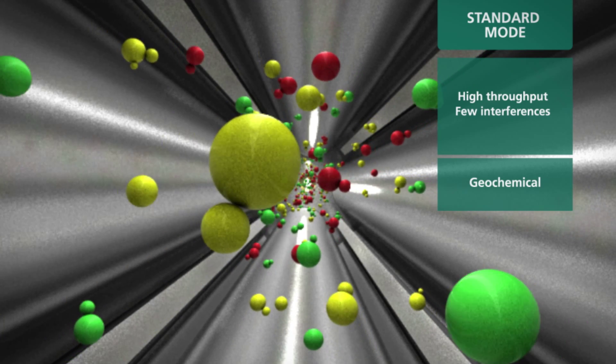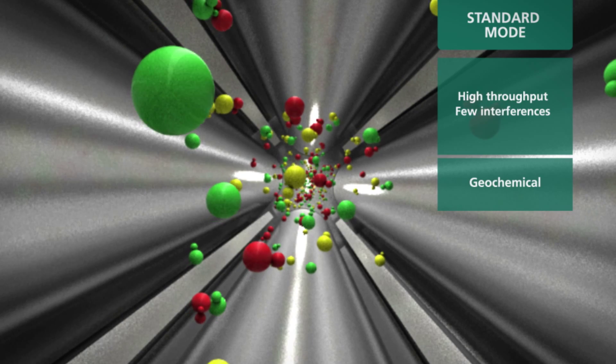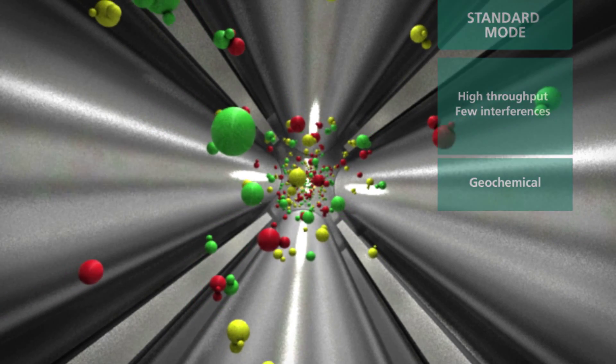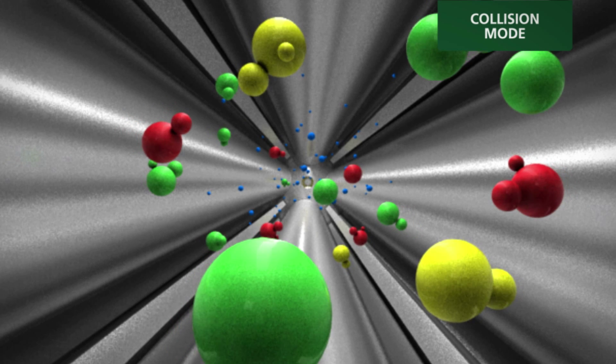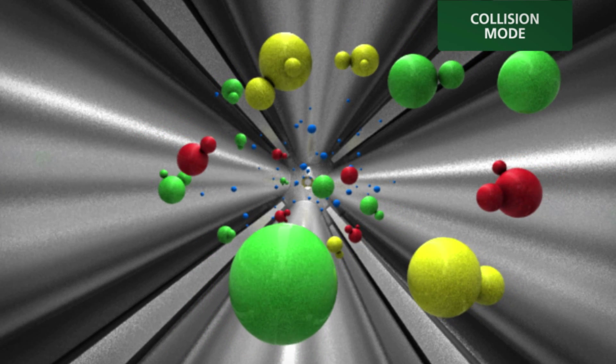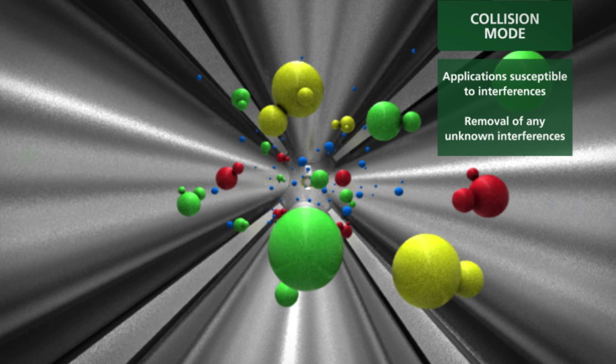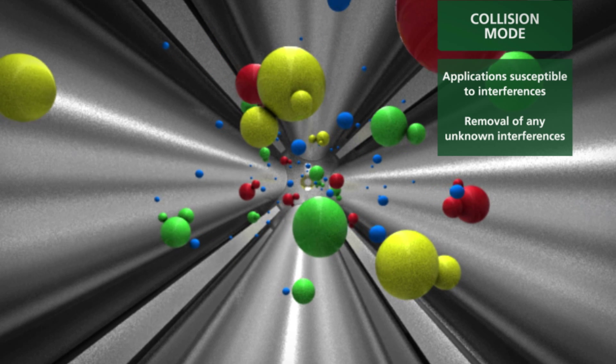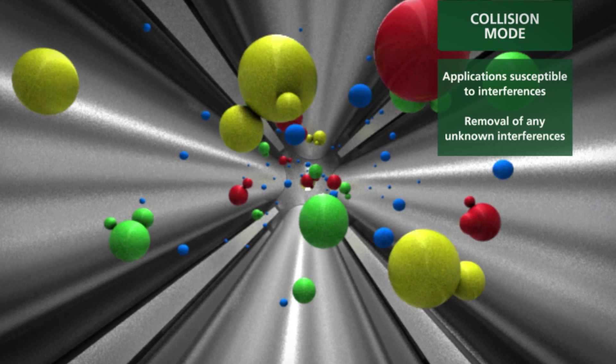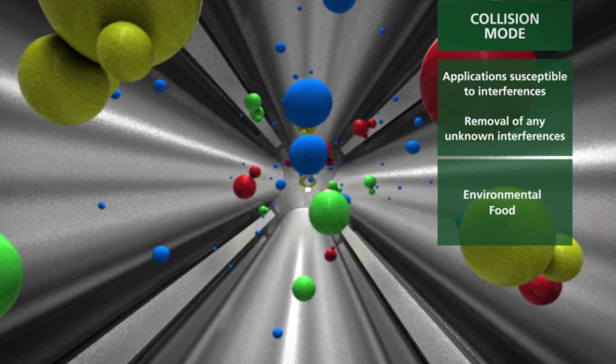If your application happens to be susceptible to interferences, or you just want the comfort of removing any unknown interferences, simply switch the instrument to collision mode. Using a simple non-reactive gas and kinetic energy discrimination, collision mode removes many interferences and provides better performance or improved detection limits than standard mode. Collision mode can be easily set up to run a variety of applications, including environmental and food safety.